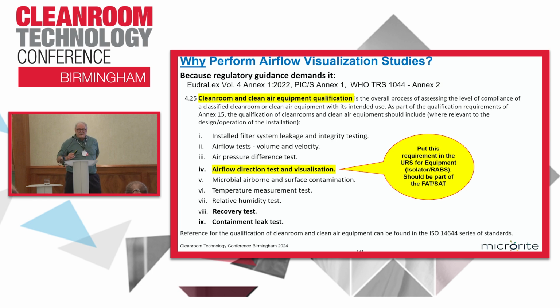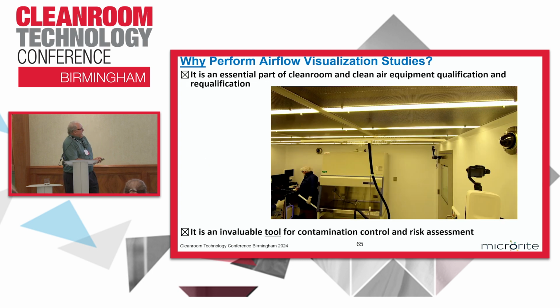But in my discussions with the US FDA, we don't care. We want to see the study. Prove to me the equipment operates correctly. Work with your suppliers to get around it. We're talking PLCs. There can be a program. It can be done. Every single installation where we put our foot down, they've gotten people in to get around that effect, because it's come back to bite the companies that tried to address the issue with a risk assessment. So make sure you plan for it. And this really is an essential part of contamination control.